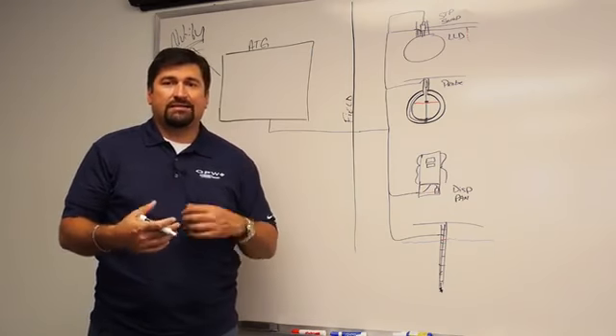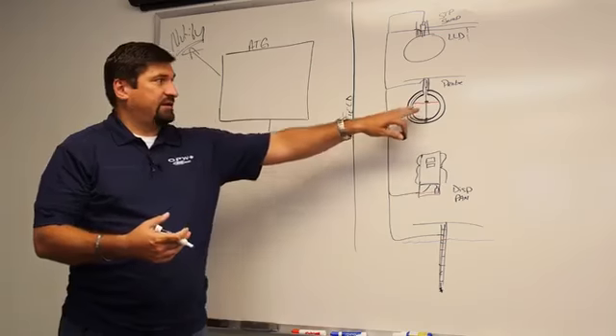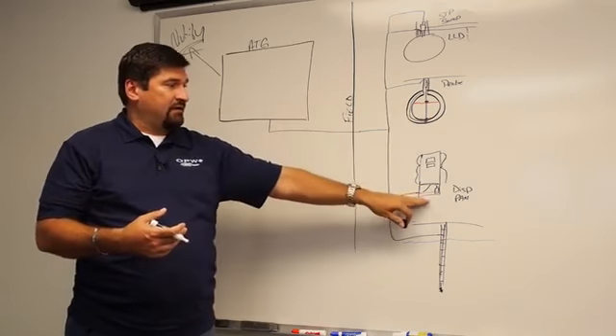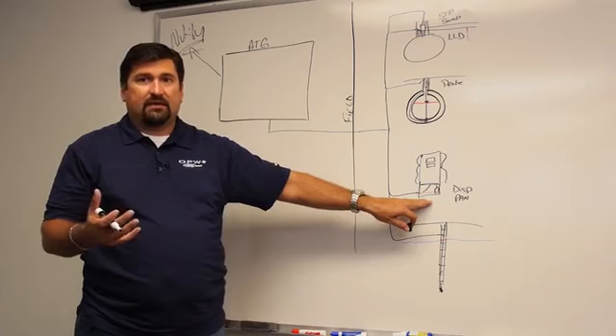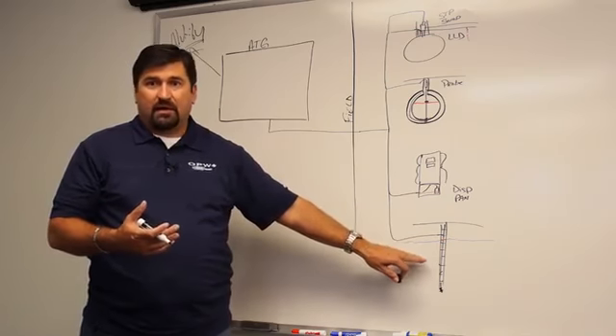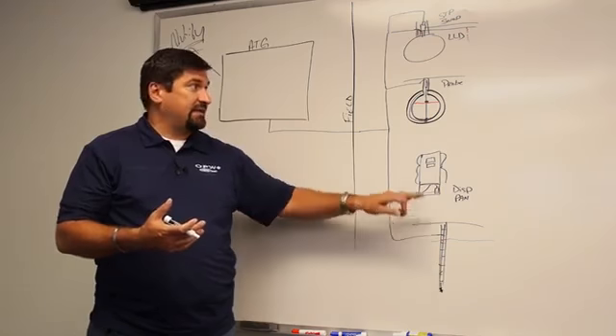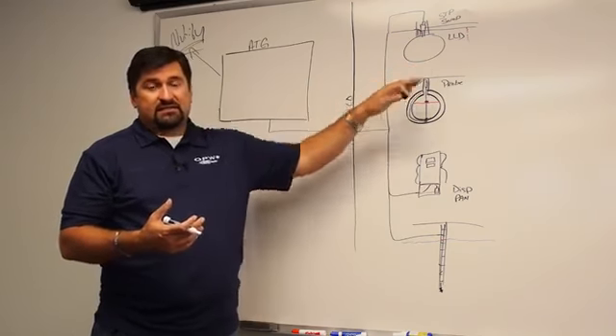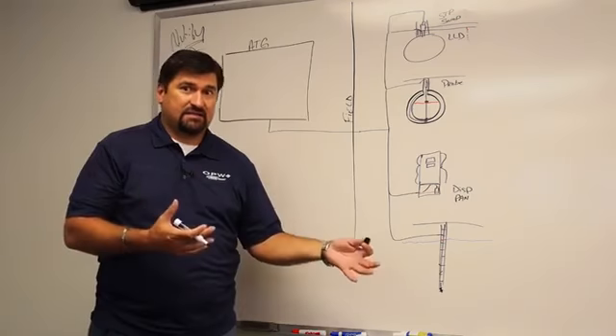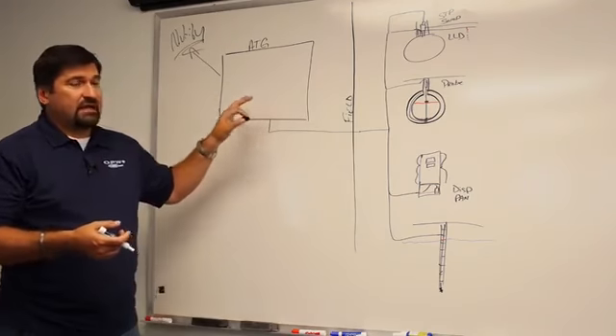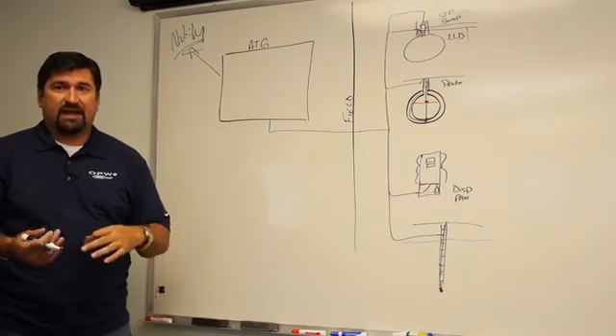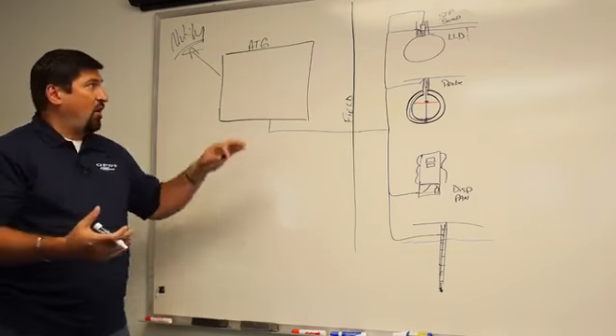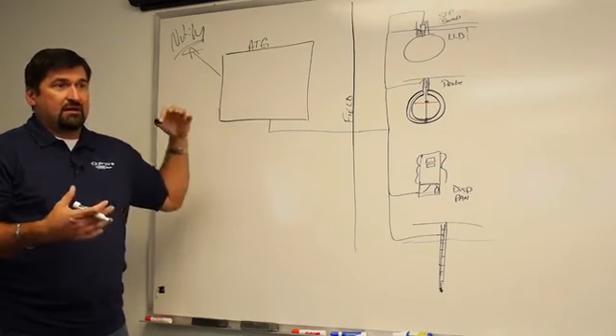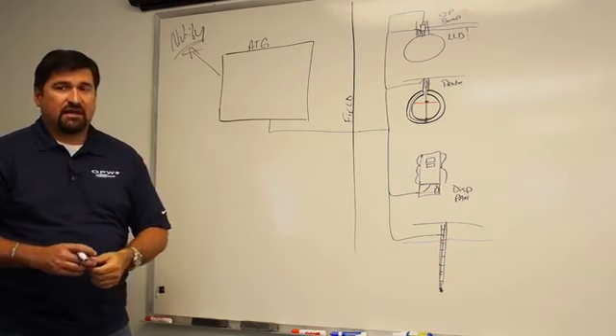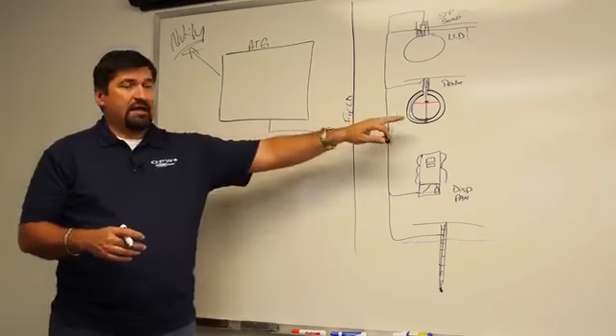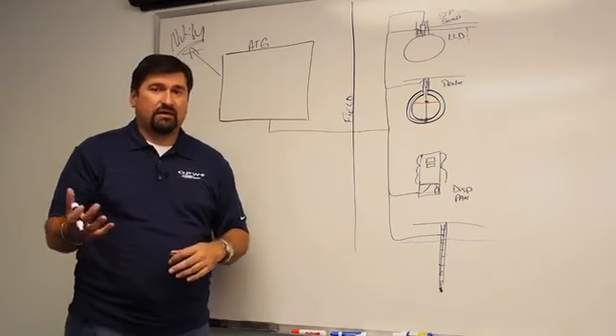Then they can dispatch somebody out there to either fix the water that's leaking into the tank, fix the union or breakaway that may be leaking underneath the dispenser, or pull up the monitoring well to see if something is leaking at the site that's not being picked up, as well as check the STP to make sure that the LLD and the STP sensors are working fine. It's designed to notify, whether by email, a fax, or a text message, to someone or through an external polling solution that monitors the station to make sure they're staying within compliance, not only for inventory management, but for your state and local regulatory requirements.